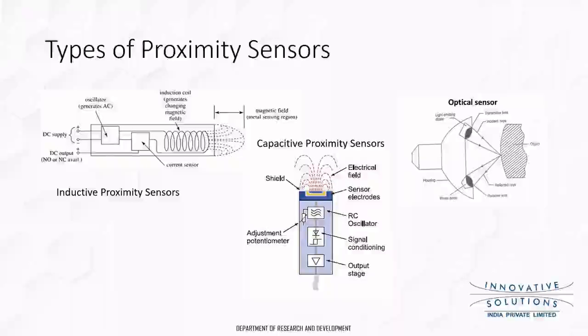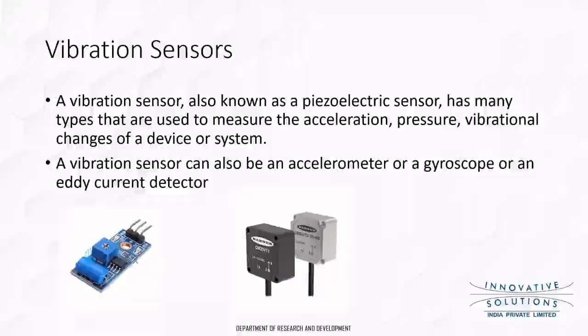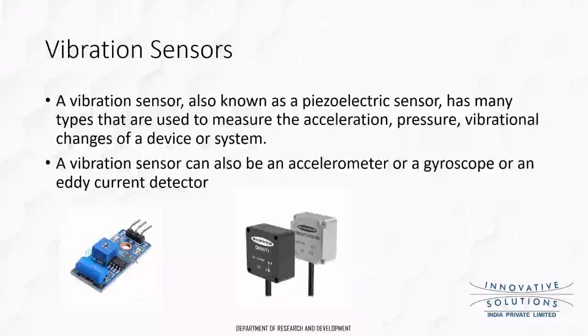So this is again an interesting sensor, the vibration sensor. Any sensor can be a vibration sensor depending on the range. So there are piezoelectric sensors. Piezoelectric sensors generate signals depending on the vibration, which is converted into an electrical signal due to the crystal inside it. So what happens in a piezoelectric sensor is that the vibration is given to a crystal, and the crystal oscillates depending on the vibration. And when the crystal vibrates, a small electrical signal is generated, and that electrical signal is measured.